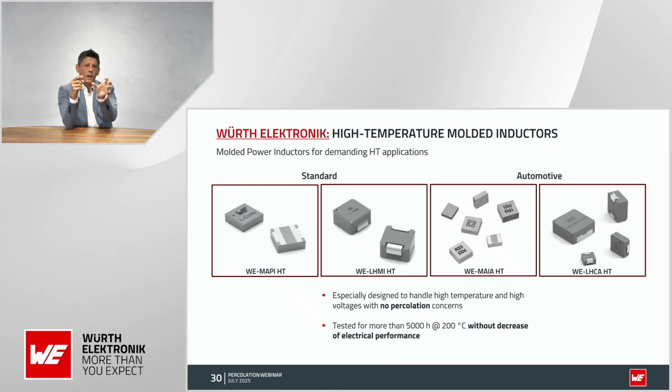Or an application where the connection point has some jumps in voltage and whatever. Then we strongly recommend you use the high temperature version of the current LHMI or MAPI from us. We tested more than 5,000 hours at 200 degrees without decrease of the electrical performance, to tell you we don't suffer percolation so you don't need to be concerned about it.